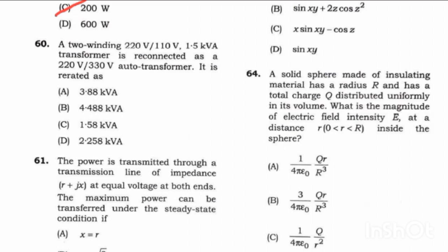Question 60: A 2-winding 220 volt by 110 volt, 1.5 kilovolt ampere transformer is reconnected as a 220 volt by 330 volt auto transformer. It is re-rated as: A) 3.88 kilovolt ampere, B) 4.488 kilovolt ampere, C) 1.58 kilovolt ampere, D) 2.258 kilovolt ampere. The correct answer is B.